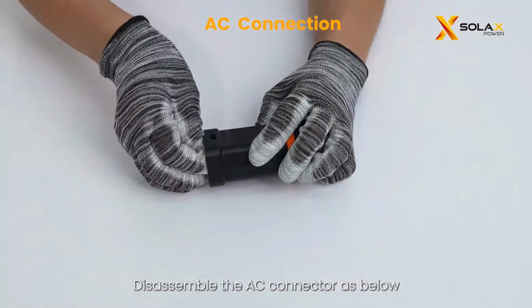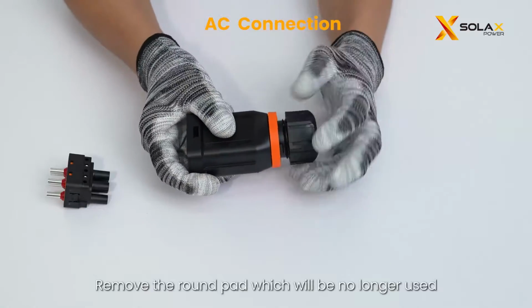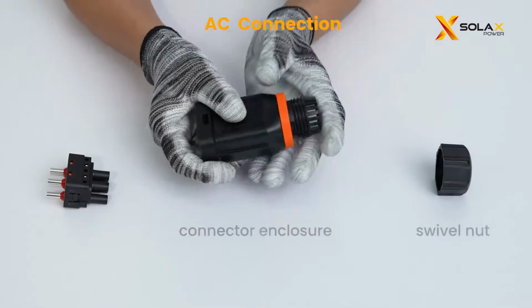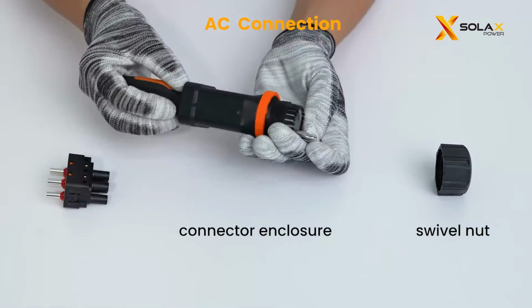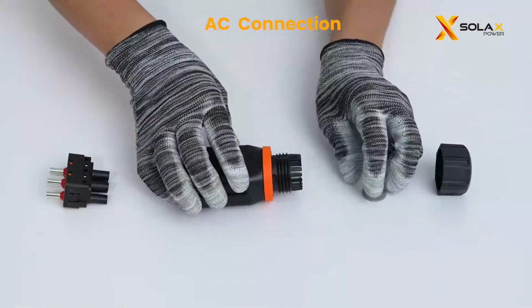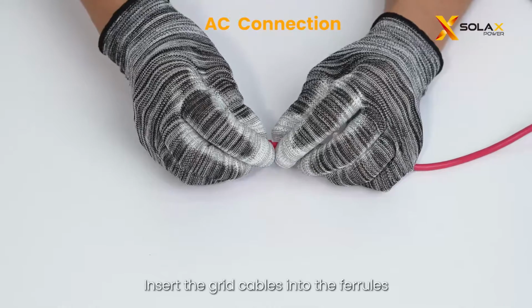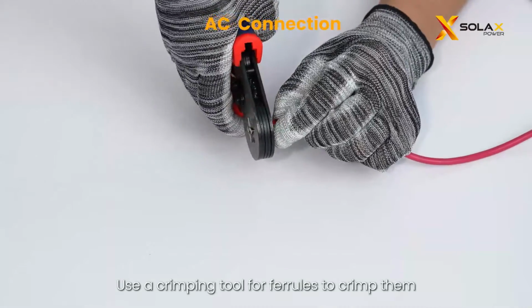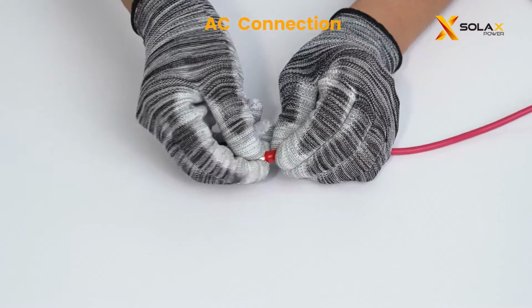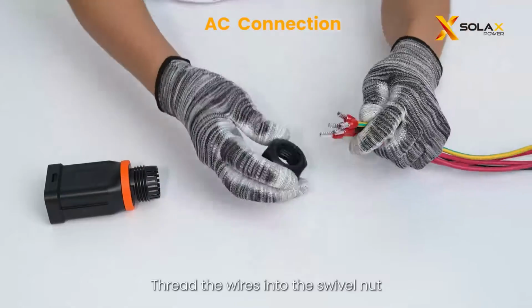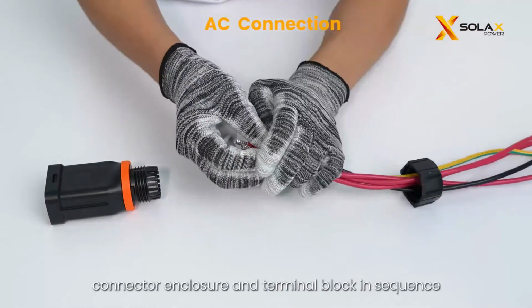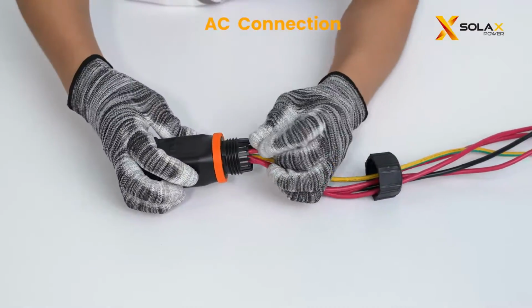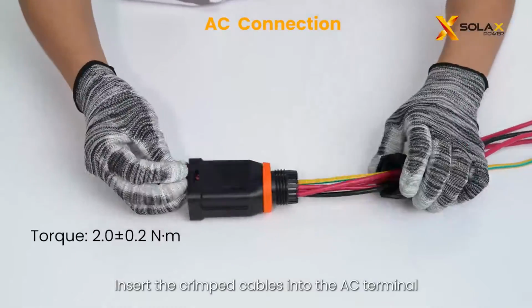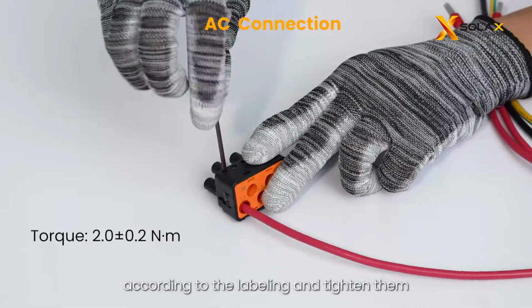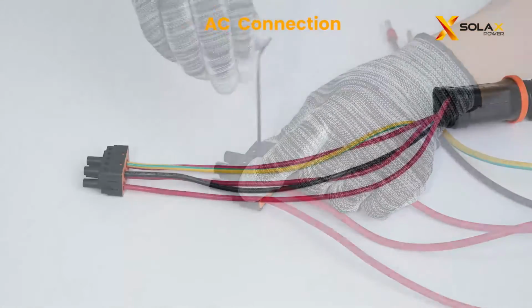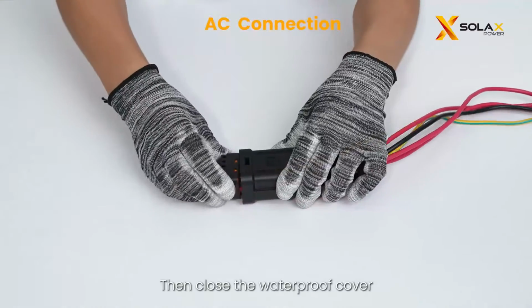Disassemble the AC connector as below. Remove the round pad which will be no longer used. Insert the grid cables into the ferrules. Use a crimping tool for ferrules to crimp them. Thread the wires into the swivel nut, connector enclosure, and terminal block in sequence. Insert the crimped cables into the AC terminal according to the labeling and tighten them. Then close the waterproof cover.